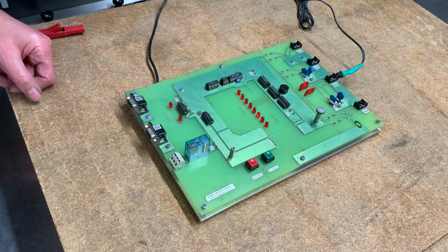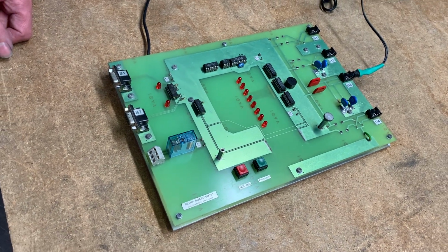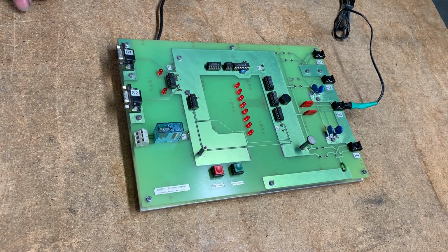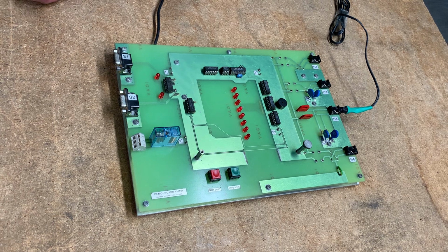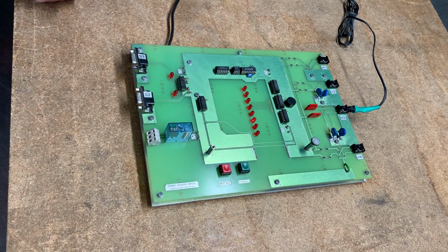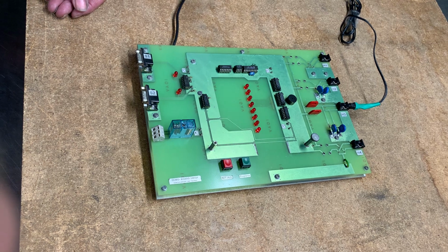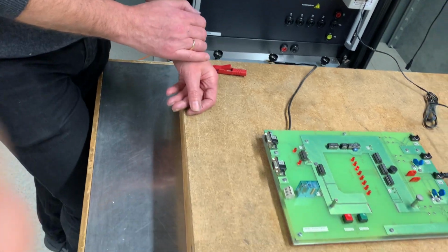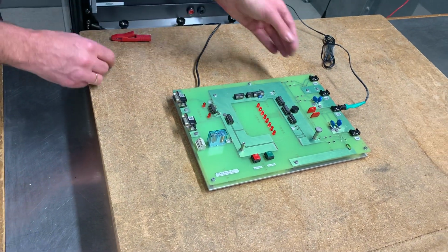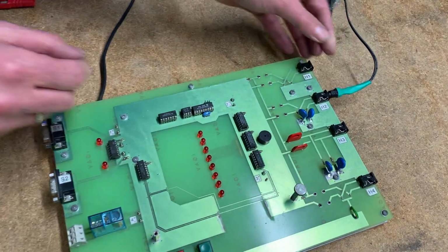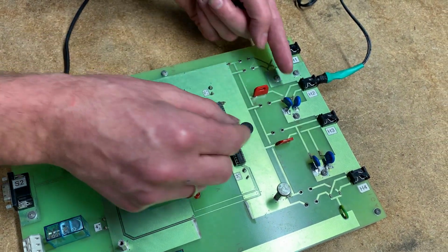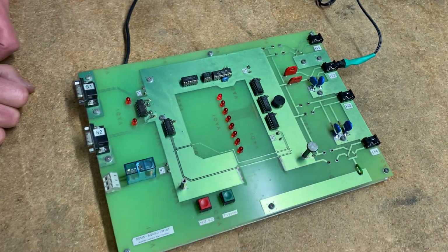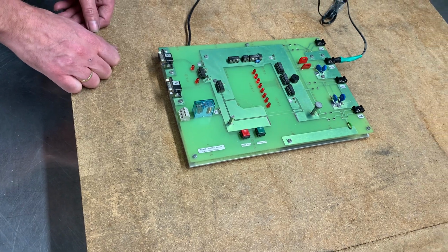When I switch it to 600 volt, there you see already effects on the LEDs. 700 volt, 800 volt. I simply increase the level. You see, more influencing, more influencing. And suddenly at 1000 volt, also the relay will switch. Now I go to the next board. There, the effects of the capacitors, not varistors, capacitors, are more effective. You see, again, no disturbances.